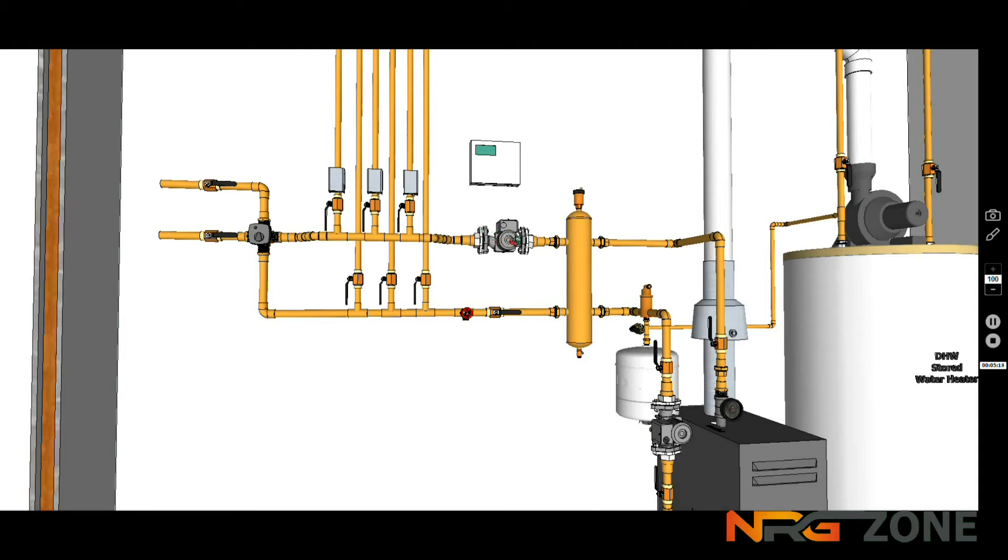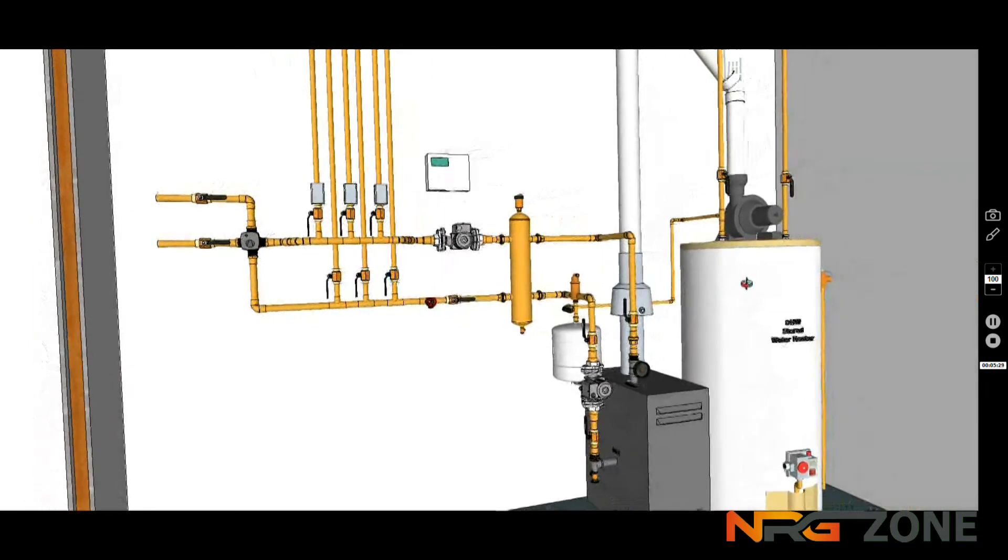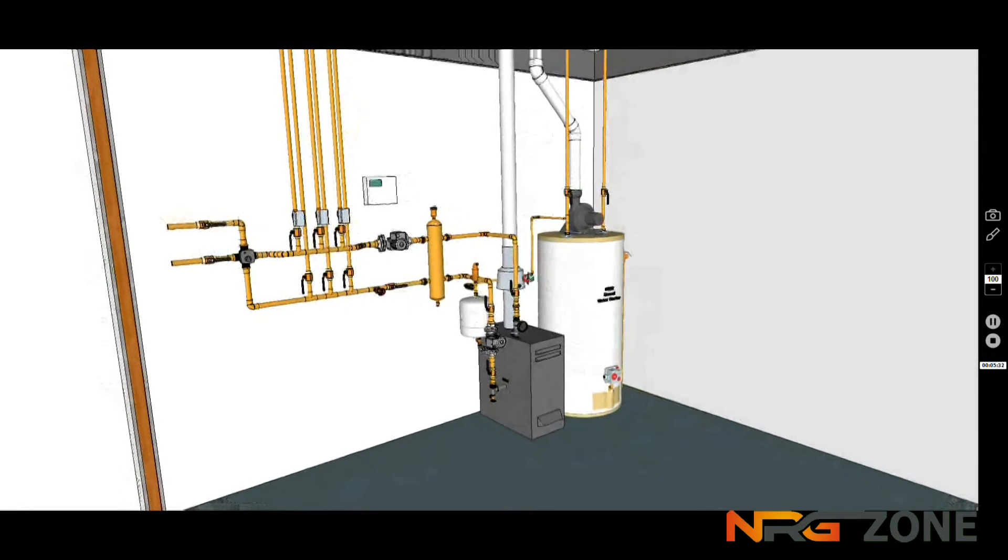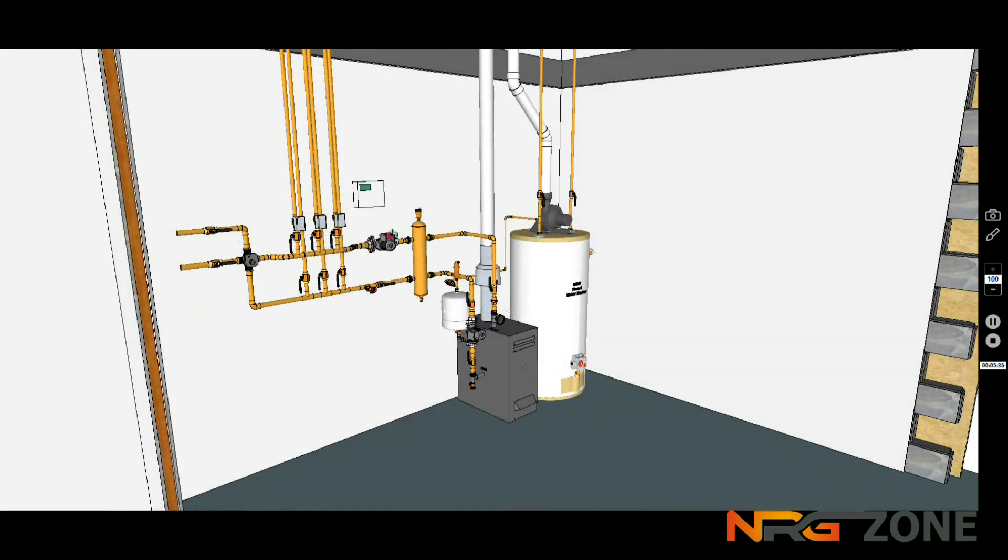Generally speaking, a fixed speed pump tends to be very, very inefficient. It certainly is against regulations now, or about to become against regulations, because they're so electricity hungry. In this situation, it's quite a lot of pipework, quite a lot of bits and pieces to put together. And there's really a lot of energy waste, because even the warm air that would be in the room, even if the pipework was insulated, you still find there's a lot of air in the boiler area that is heated. And that's the very air that's been drawn into combustion and fired up the chimney and out and away from the building. So the whole system, to my mind, is very energy inefficient, and it really needs to be looked at.